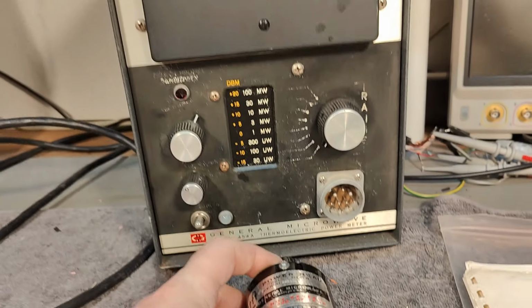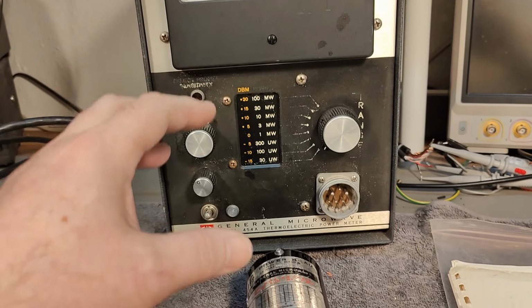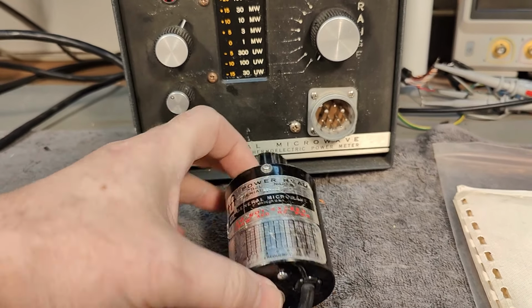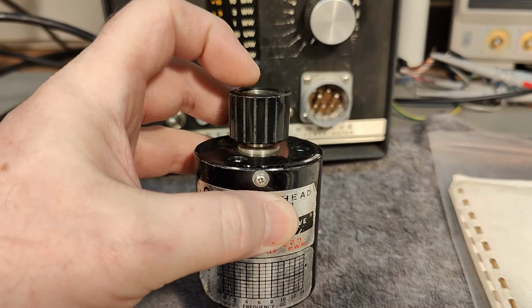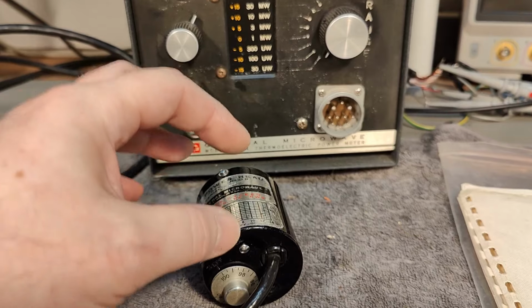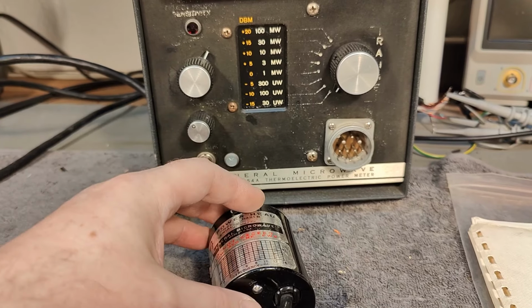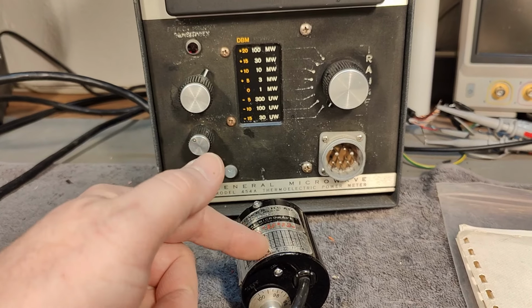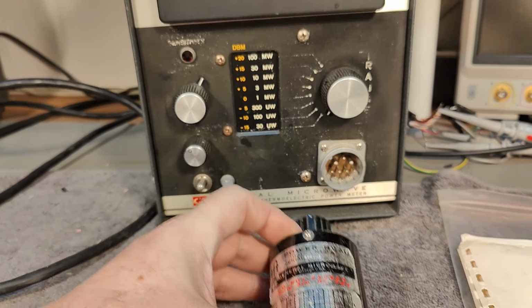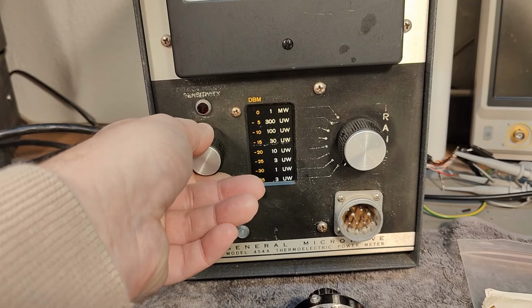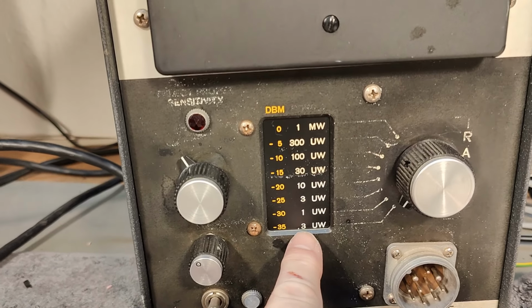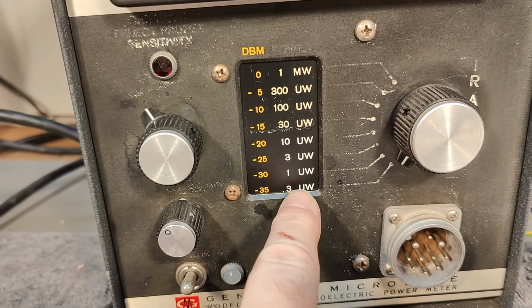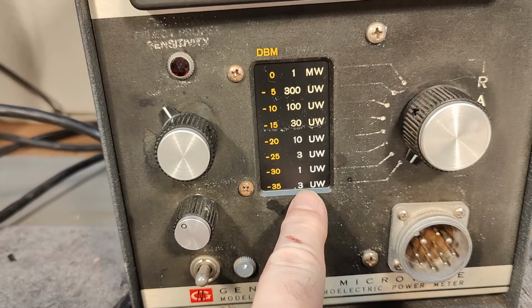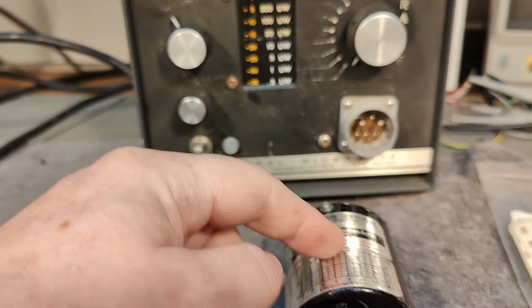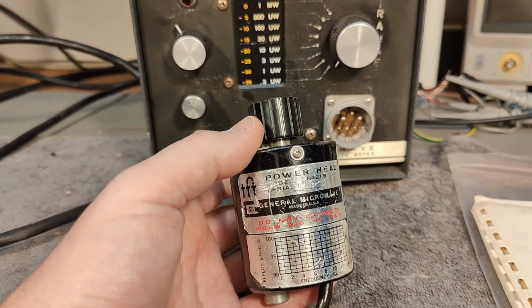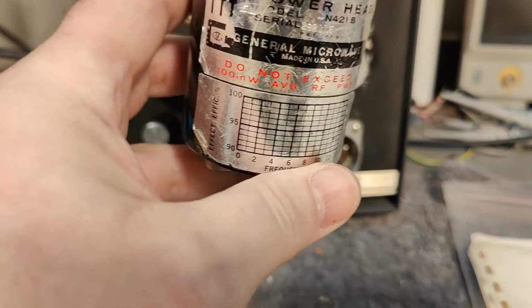So the idea is this system here measures actually the temperature rise on the sensor that is connected to the input and compare it with the ambient temperature. That means that will be your input power, the power that is needed to warm up this one, right? So you can imagine full range 0.3 microwatts. That is the power needed to warm it up to full range. I don't know if you're a little bit impressed, but I am.